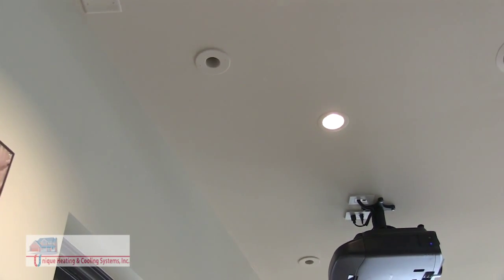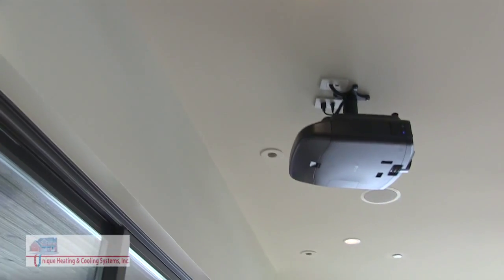So on a high velocity system, rather than coming out of, say, a 4x10 ceiling register, all the air is distributed out of 2-inch high velocity lines, and then the sound is canceled right at the diffuser so that it is quiet.